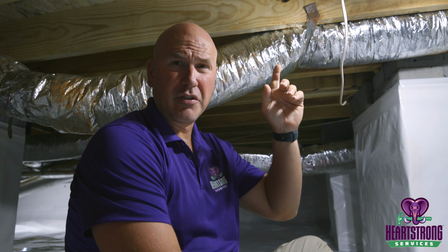When we first came out to this house, if you remember, we had subfloor insulation that was still in the crawl space. We had a lot of fungal growth on the wood down here. We had a problem with water intrusion after periods of heavy rain, and we saw that with all the mud and silt staining that was on top of the plastic. And of course, we had a very high humidity problem down here because of air exchange, as we talked about in the previous video. So I want to take a moment and just recap what we've done.